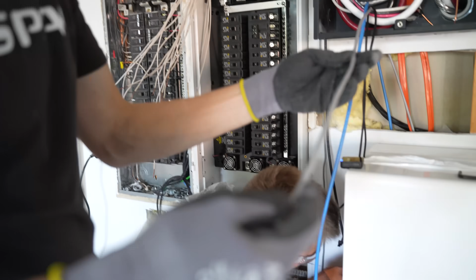All wire in a conduit must be rated for the highest voltage present. That's real important. You can mix AC and DC wire in a conduit, but not in certain circumstances, such as photovoltaic DC output, so you've got to know your rules. There are about 1,000 pages in the 2023 code book, and code updates every 3 years, so they're always throwing a curveball at you.